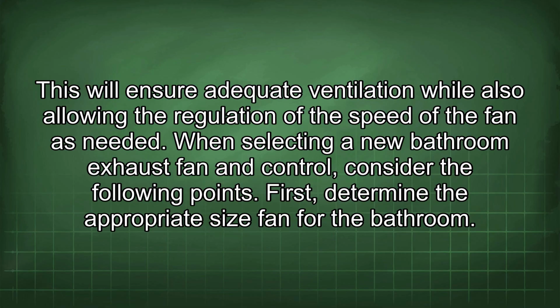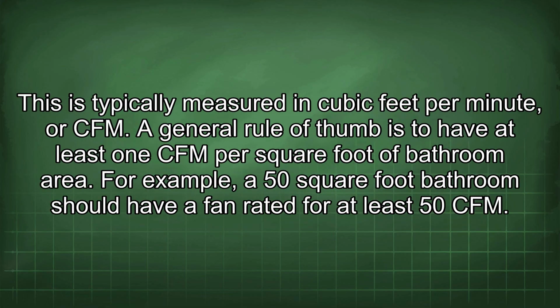When selecting a new bathroom exhaust fan and control, consider the following points. First, determine the appropriate size fan for the bathroom. This is typically measured in cubic feet per minute or CFM. A general rule of thumb is to have at least 1 CFM per square foot of bathroom area. For example, a 50 square foot bathroom should have a fan rated for at least 50 CFM.